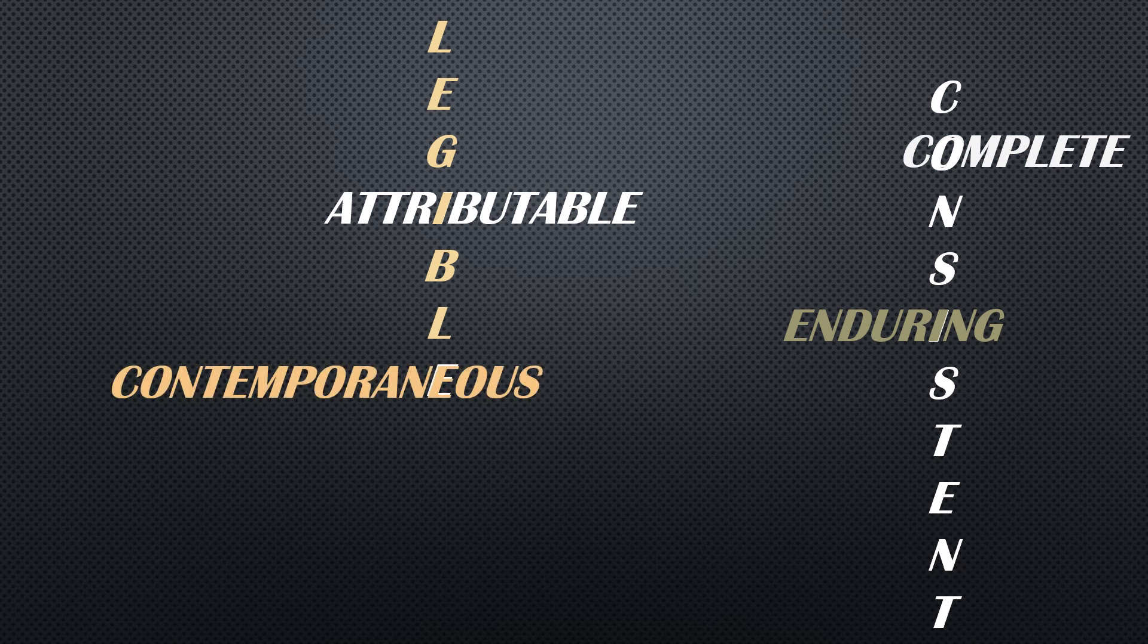Coming to the next word: Contemporaneous. Whatever data we are going to enter must be contemporaneous, so at the time it is performed you must enter the data. Spontaneously you need to enter the data - what you have seen, what is the result - there must not be any manipulations. Data should never be backdated. This is a very important point during good documentation practices. You can never backdate data, and also do not enter the results before performing the test. Data must be entered at the time it is being performed and should flow in order of execution to be credible.